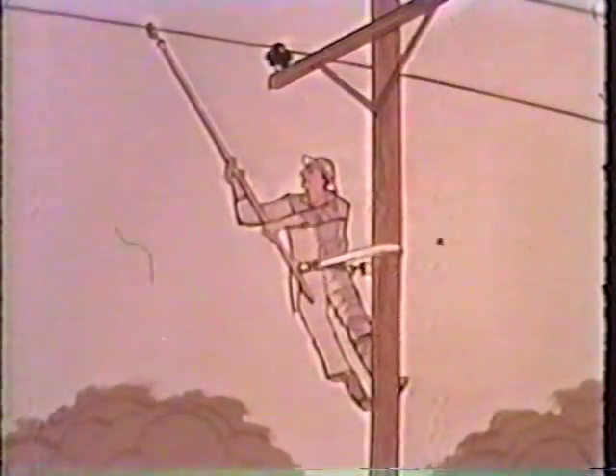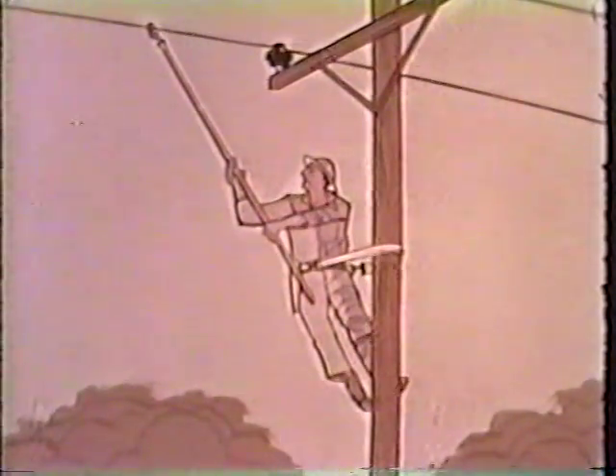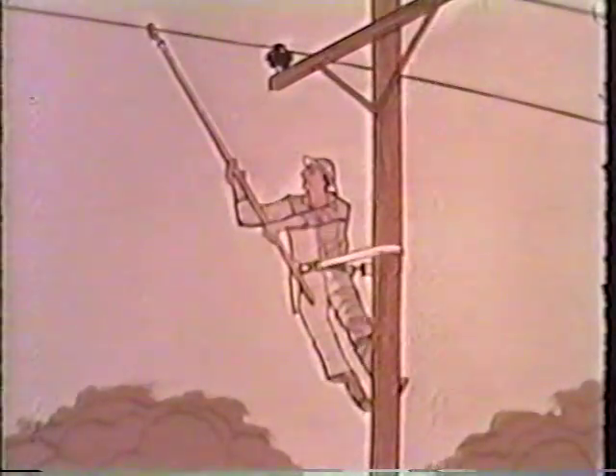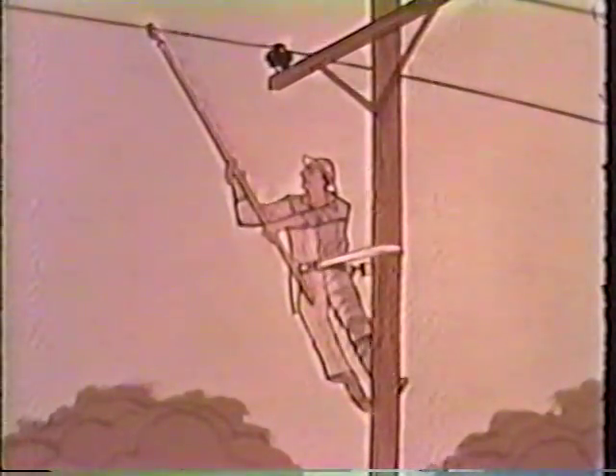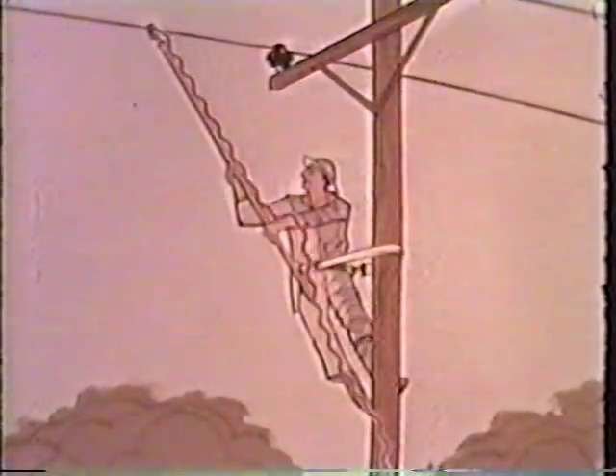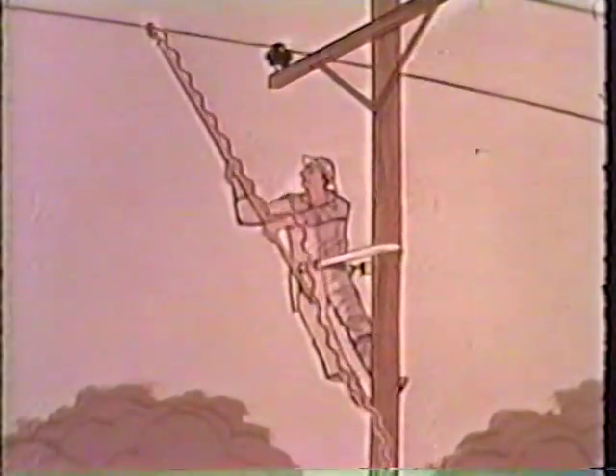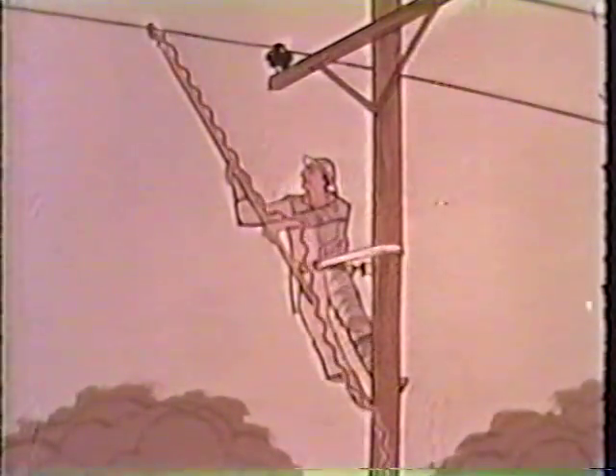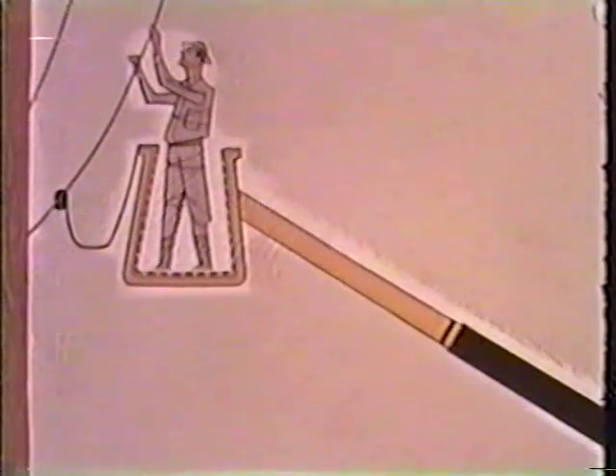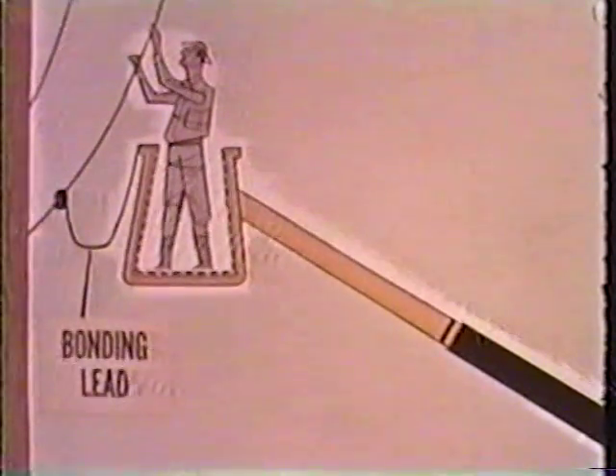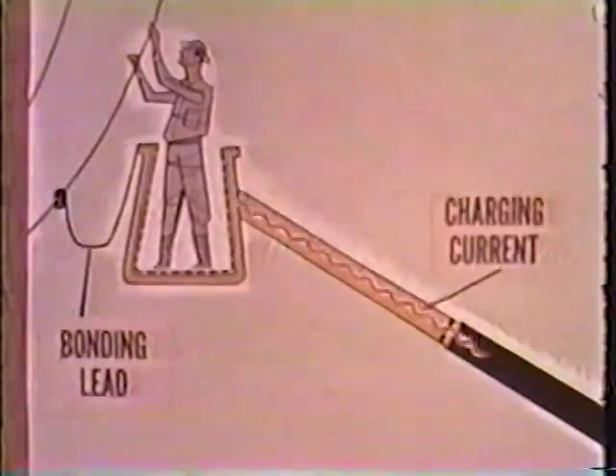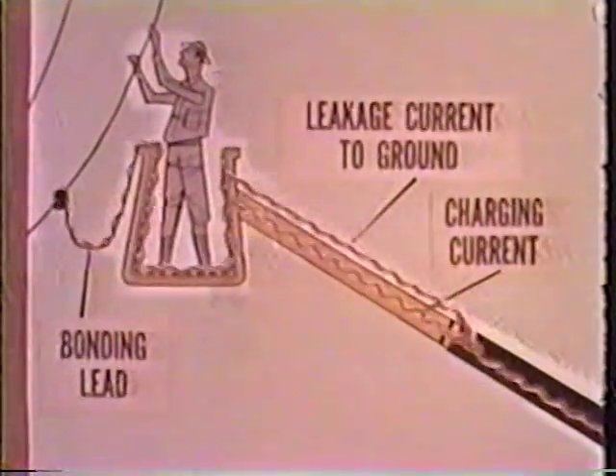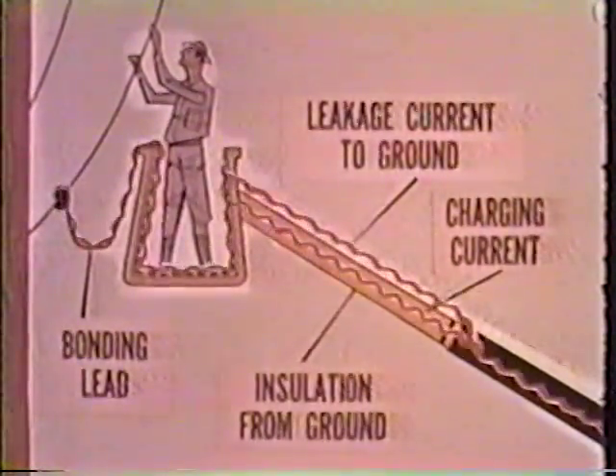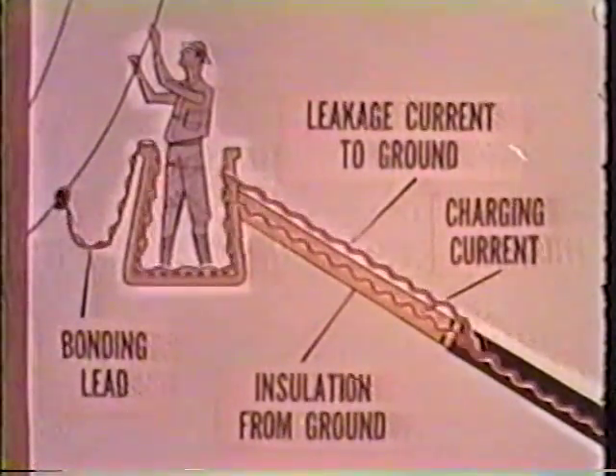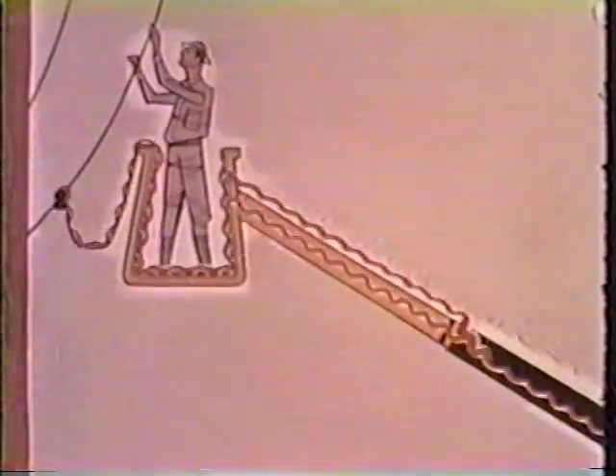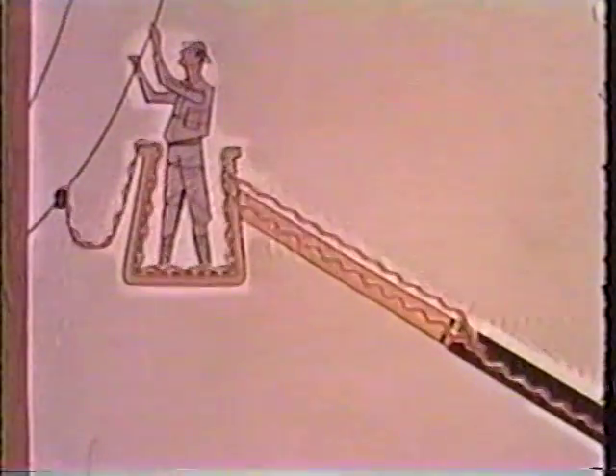This illustrates a basic difference between the barehand and the conventional hot stick method of live line work. With the hot stick method, any leakage currents which might pass over the insulated stick from the conductor to the pole must also pass through the body of the lineman. With the barehand method, with the bonding lead attached to the conductor, a nominal charging current and the leakage current, if present, flow over the insulating section through the metal parts of the elbow and on through the truck body to ground. The barehand lineman is thus outside the arm current path.